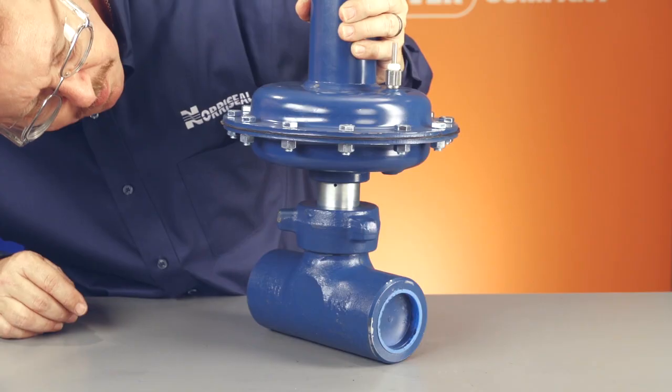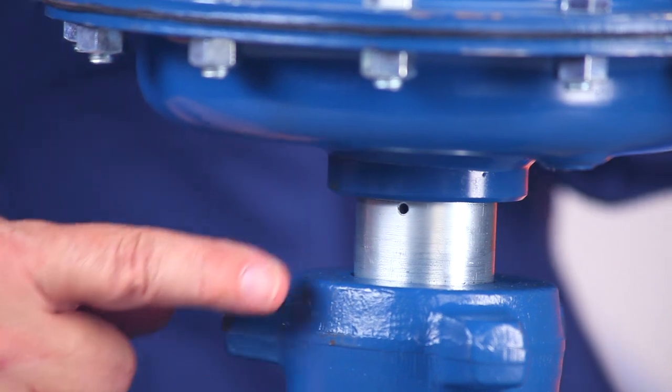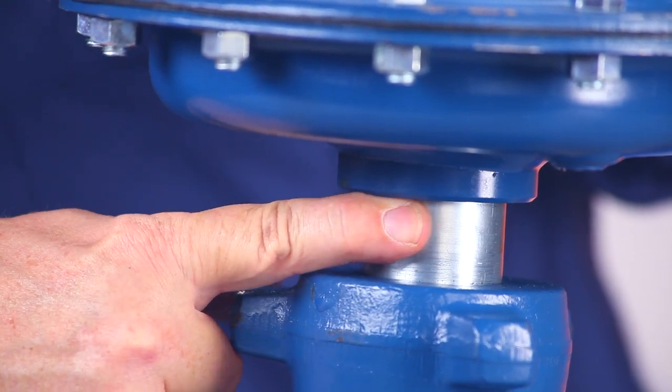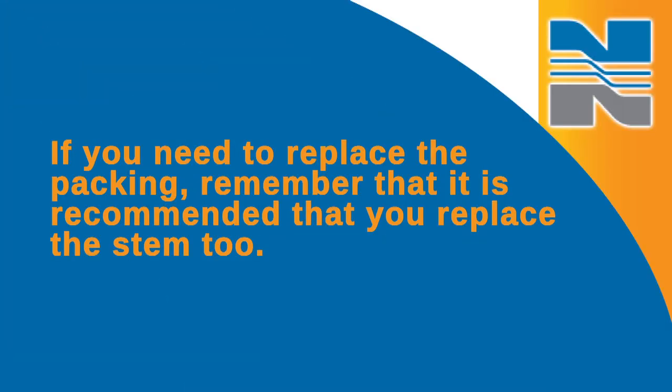The packing is easy to check. Just take a look at the vent hole on the side. If it's leaking, it means the packing has been damaged. If you need to replace the packing, remember that it's recommended that you replace the stem too.